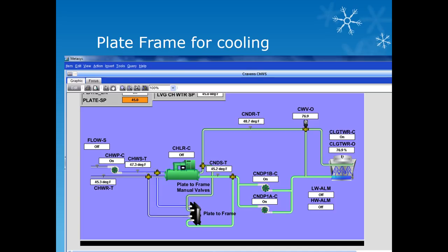In this screenshot we see a typical layout for the plate frame for cooling. The plate frame heat exchanger is shown at the bottom of the screen. You can see how the heat exchanger is tied into both the primary side and the condenser side of the chilled water system. On the condenser side there is some type of antifreeze added to the water to keep it from freezing during extreme cold temperatures. The water flowed over the cooling tower is cooled by outside air and then pushed through the plate frame heat exchanger by the condenser pumps. On the other side of that heat exchanger is the chilled water pushed through by the chilled water pumps, then distributed to the air handlers by the primary or secondary chilled water pumps.